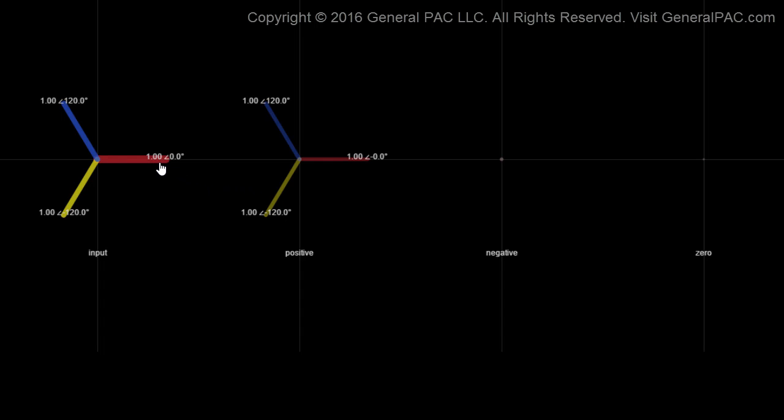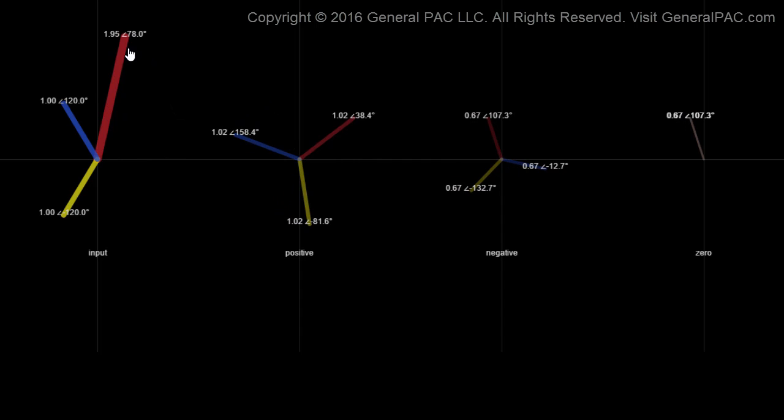Now what would happen if we change our system phasors? Would we get the same result? Let's make our system, which is a balanced system, into an unbalanced system. We could either change the magnitude of one of the phases or we change the angle. So let's pick up phase A and change the magnitude. As soon as we change the magnitude and angle of phasor A current, we see that the positive sequence component changes, but at the same time we also have a negative sequence component and a zero sequence component.